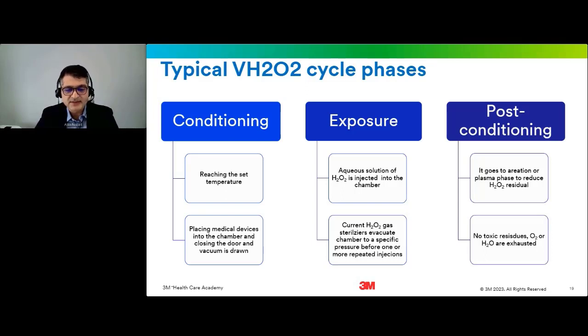All medical devices are placed into the chamber, and the process starts with a deep vacuum to remove the air from the chamber. In this phase, the sterilizer reaches the set cycle temperature. Please note that if there is residual water on the devices, it can evaporate, and it will cause longer vacuum time, and it may lead to an aborted cycle. It depends on how much moisture there is.